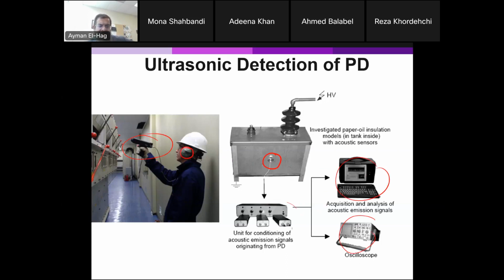You see here, these headphones basically change the signals from the ultrasound to something that you can hear. You can play with the frequency. One way to do that: this is the ultrasonic signal, a very high frequency. You take the envelope of the signal, detecting only the envelope. There is a technique for that, and then you pass it through a low pass filter to get rid of the high frequency components. Now this is a low frequency component that you can hear.